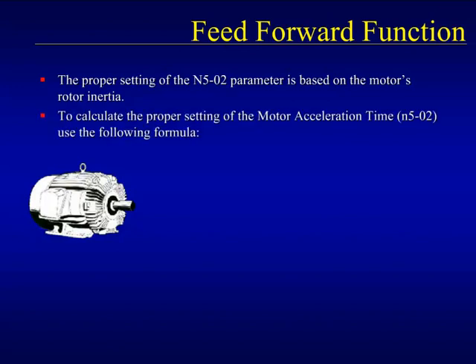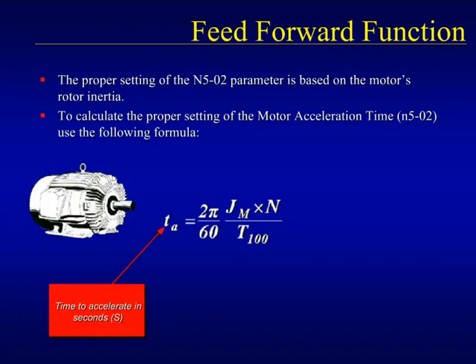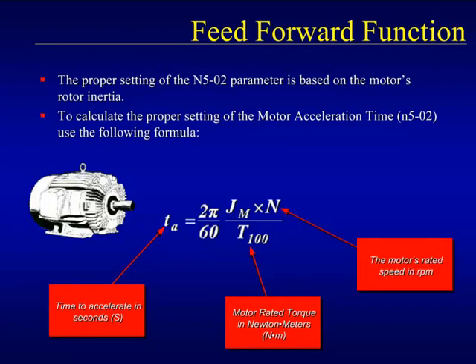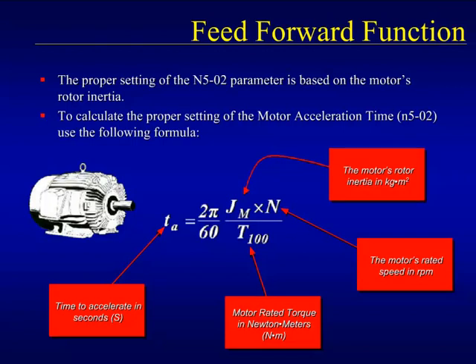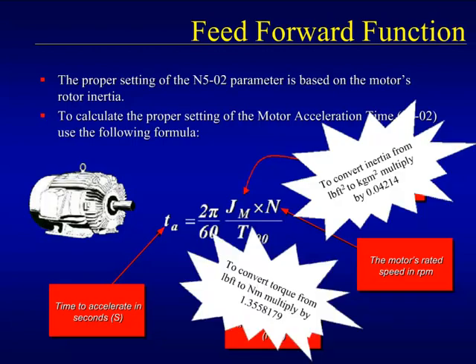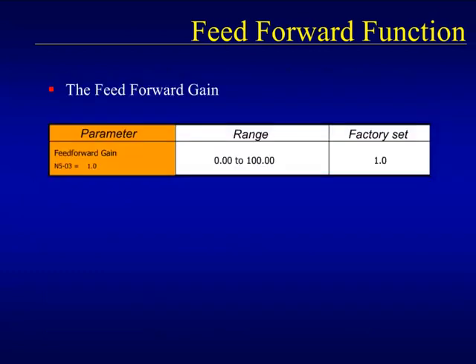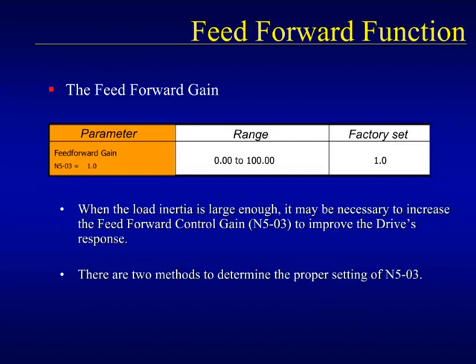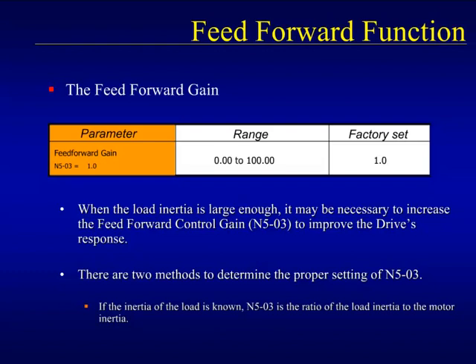Calculation of N5-02 will require the use of the formula shown here. T_A is the program time to accelerate to speed. T_100 is the motor's rated full load torque. N is the rated speed of the motor. J_M is the rotor inertia of the motor and can be found by contacting the motor manufacturer. The formula uses metric units so the English to metric conversions for both the torque and inertia are also shown. Parameter N5-03 is the feed forward gain parameter. When the load inertia is larger than the motor's rotor inertia, it will be favorable to include it as part of the feed forward's compensation calculation. The proper setting of N5-03 can be reached one of two ways: if the ratio between load and rotor inertia is known, set that ratio as the feed forward gain; if the load inertia is not known, use the technique shown on the next slide to measure it.